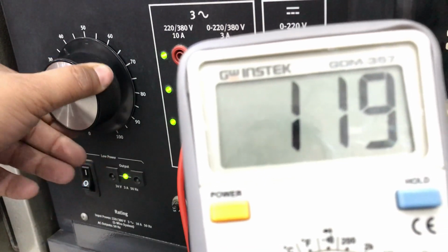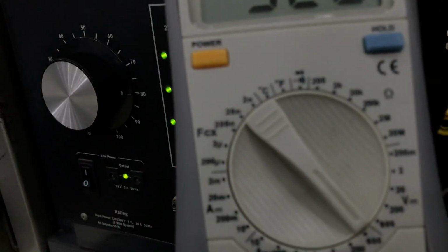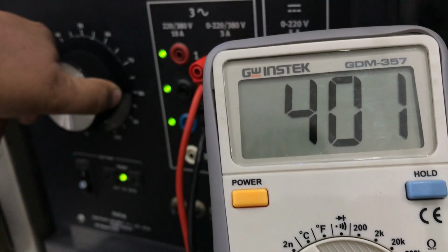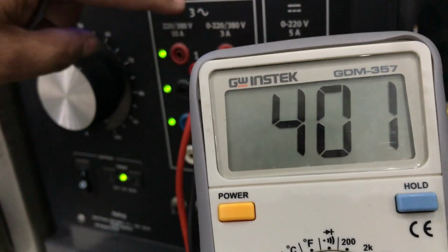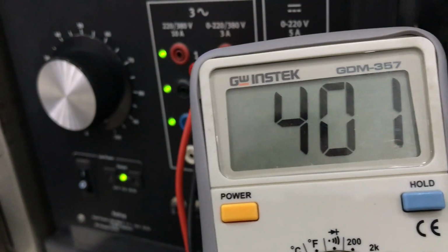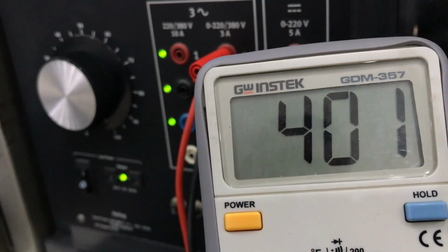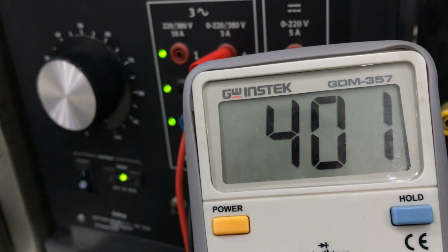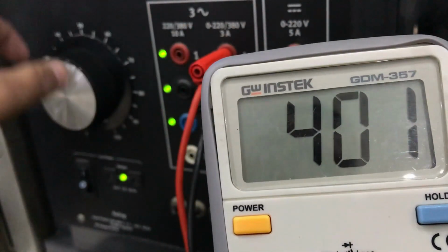Let's see what is the maximum variable voltage at AC I'm going to see. If you can see, my settings are at AC voltage. The maximum that I'm getting is about 400. Why? It's supposed to give you 380 volts. Why am I getting 400? Because there is no load connected. Once you connect the load, it should maintain that 380 volts. And just to remind you, in South Asia, normally the voltage coming out from your transformers is 440 volts. But in North America, that might be different. So that's why you're getting that variation.